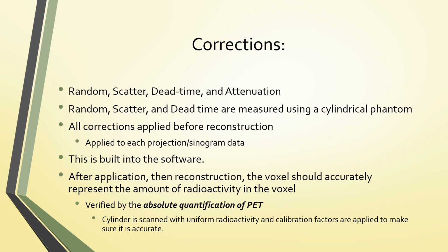After application, then reconstruction, the voxel should accurately represent the amount of radioactivity in the voxel. And this is verified by the absolute quantification of PET. The cylinder phantom is scanned with uniform radioactivity, and the calibration factors are then applied to make sure that it is accurate.